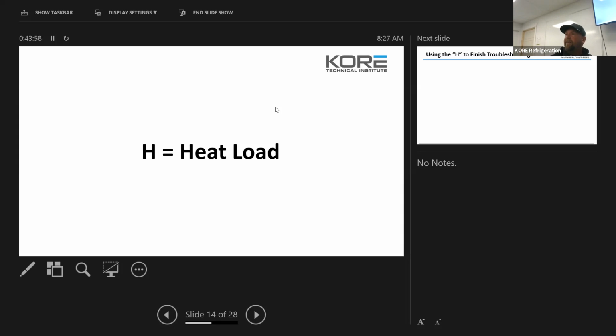It could be a lot of things, but for whatever reason, flash gas is when, going through your heat cycle, that condenser is supposed to not only reject the heat off of that gas, but then turn that gas into a liquid, right? And then it's supposed to subcool the liquid to the tune of 12 to 15 degrees. So when you're subcooling, you're taking extra heat off. So any heat pickup it gets between there and the TXV doesn't boil back off into a vapor, because what do you want going to a TXV? A solid column of liquid, not just some liquid. The more liquid you send there, the more efficient that expansion valve is. If you don't condense fully, you're going to get less heat pickup because there's still heat in that refrigerant from the last time it went through the cycle.